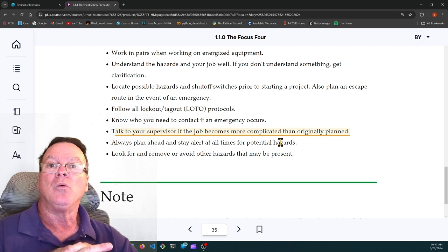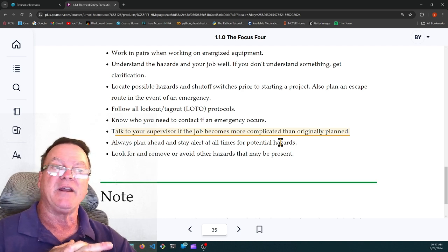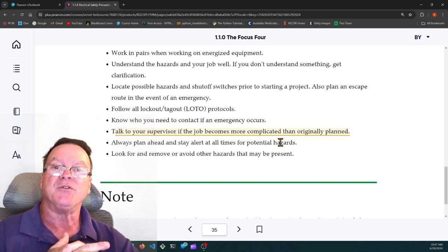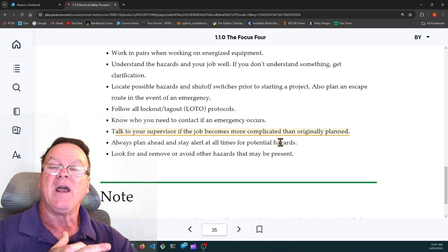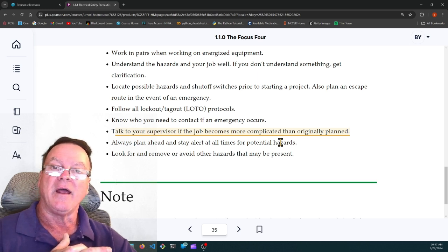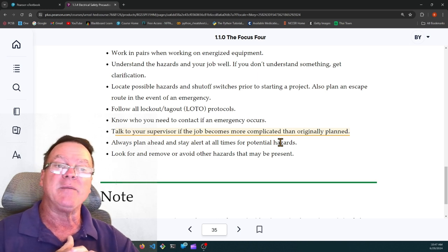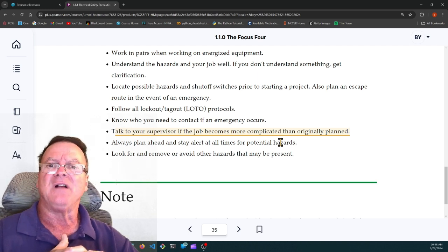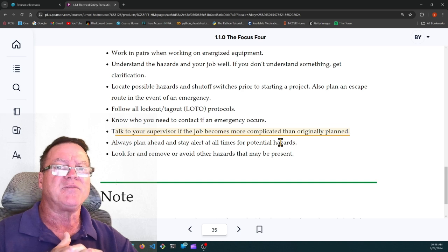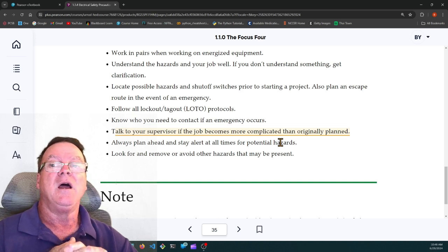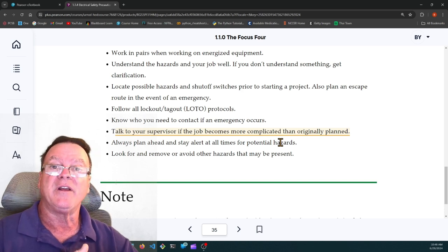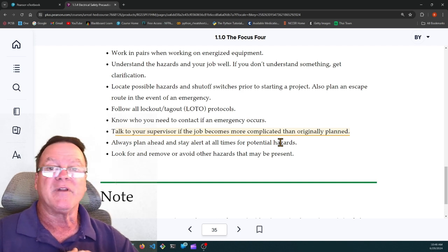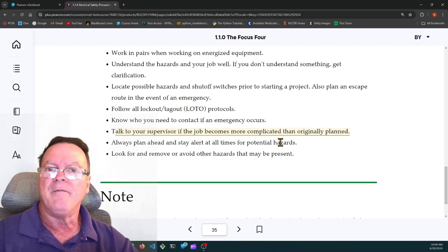You're going to take an arc flash plate off of a panel, and you're just going to terminate a number 10 wire on that circuit breaker. When you go to turn the circuit breaker off, you find that it is damaged. It's cracked in half. It's still on the stabs. It's still energized, but that circuit breaker is no good. Stop what you're doing. Put the arc flash plate back on and go talk to your superintendent, your supervisor. Some people think, well, I saw a spare circuit breaker. We'll just go ahead and change this one out. No, that's when a lot of accidents happen.